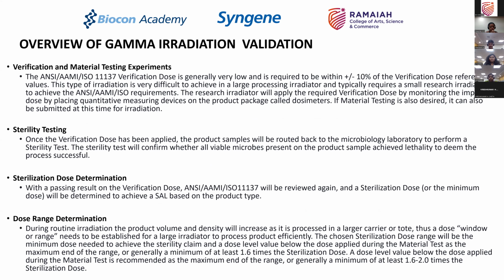You do this verification at a small research irradiator, do the study on the materials, and also do the study on the sterility testing. This is not just one experiment; you have to do multiple experiments and show repeatability as per ISO guidelines, subjecting the product under the same conditions at least 3, 4, or 5 times at the same dosage rate, and do a verification of the material, verification of the dosage, and verification of the sterility, so that you are 100% sure that the dose you are determining will do its job of sterility assurance.